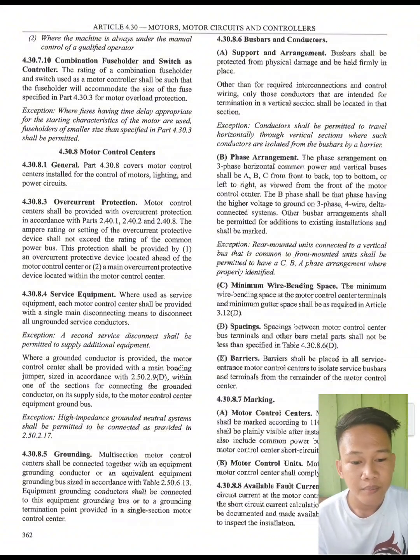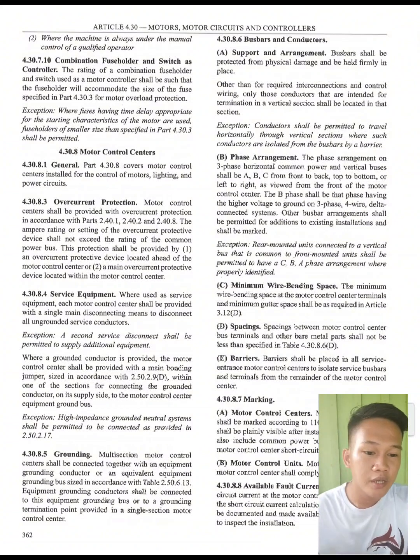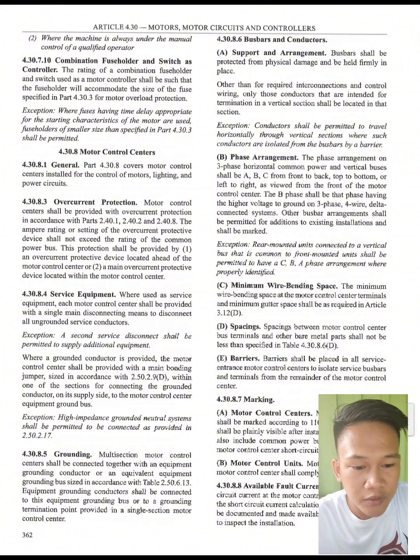So, minimum wire bending space. The minimum wire bending space at the motor control center terminals and minimum gutter space shall be as required in Article 3.12d. Spacings between motor control center bus terminals and other bare metal parts shall not be less than specified in Table 4.30.8.6d. So, next is barriers. Barriers shall be placed in all service entrance motor control centers to isolate service bus bars and terminals from the remainder of the motor control center.